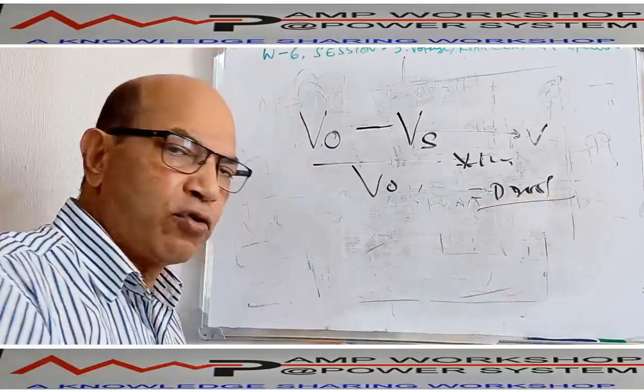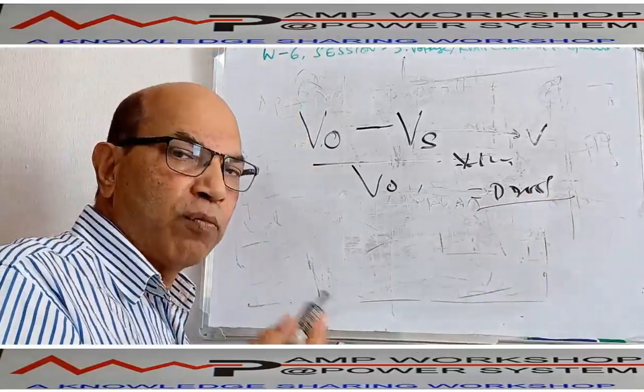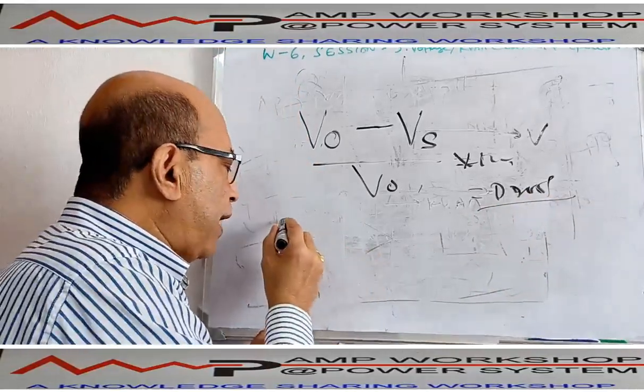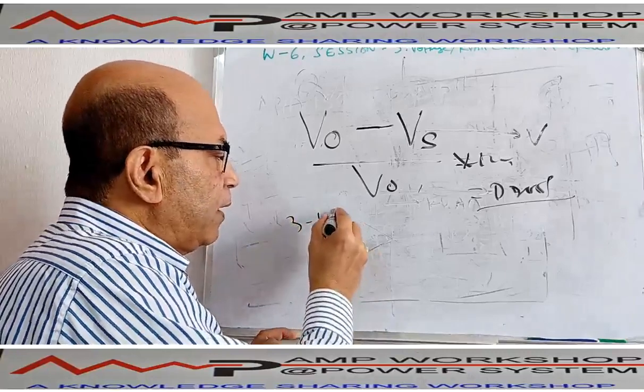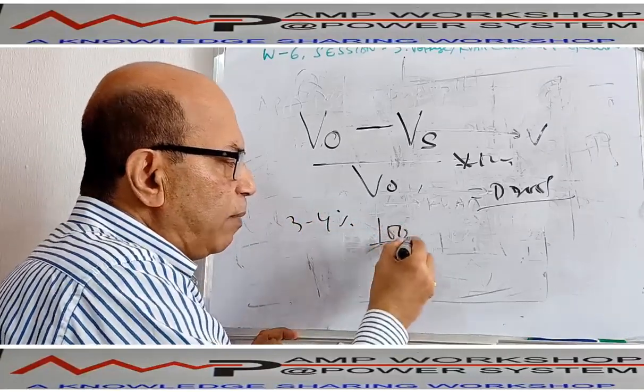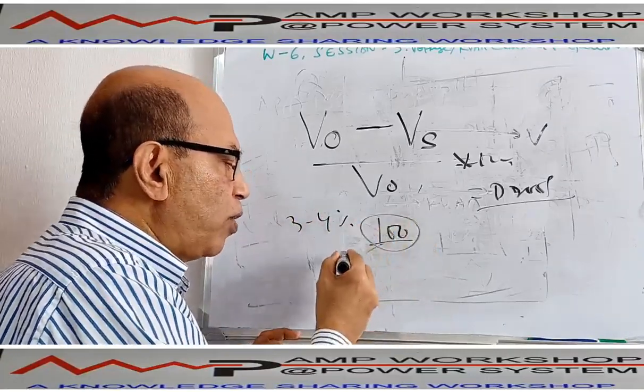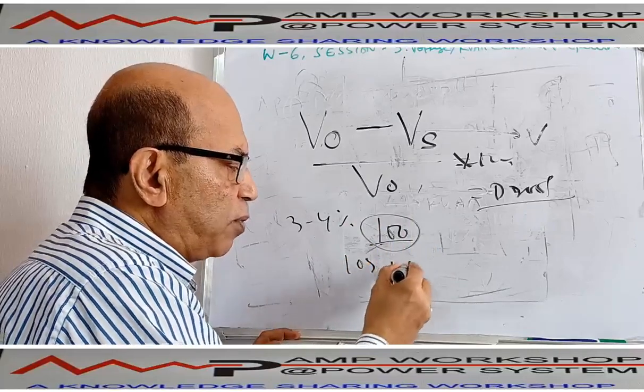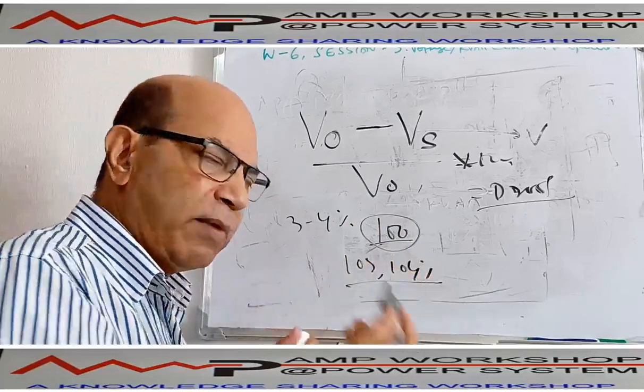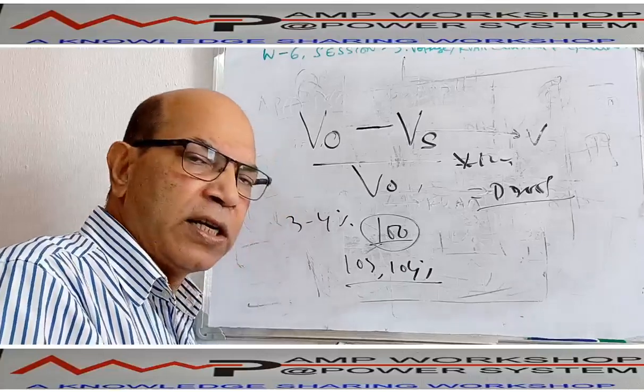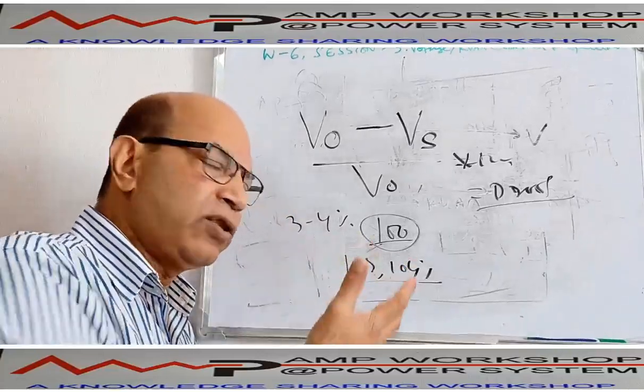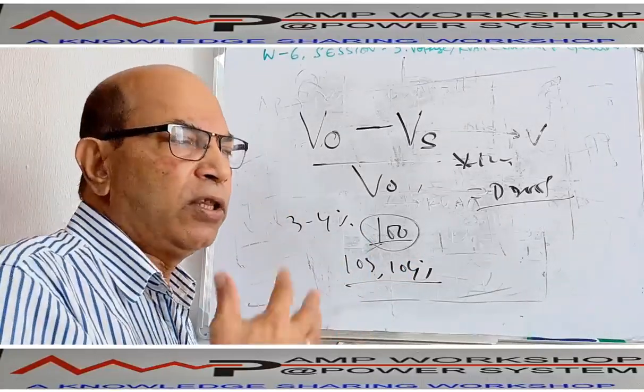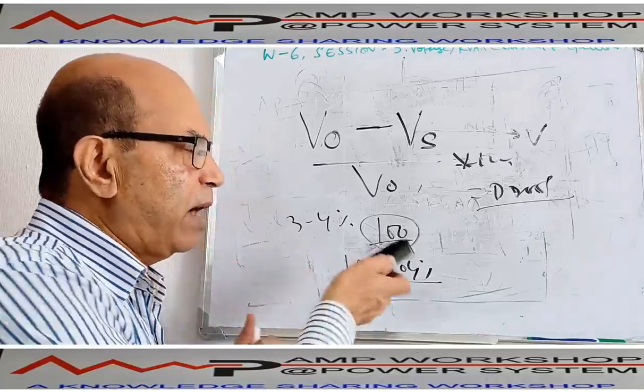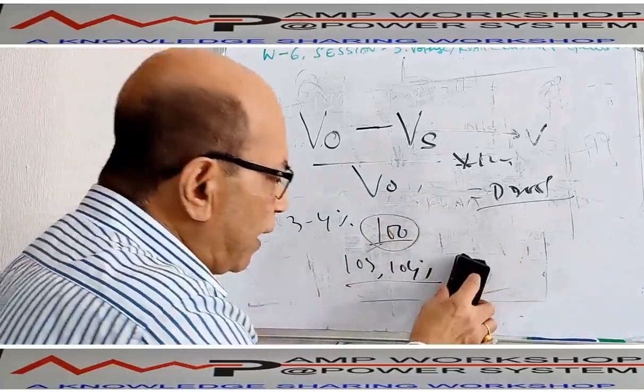Normally, when we want to run the generator in droop voltage mode, the droop setting varies between 3 to 4%. That means if 100% is the rated voltage, then you can put the droop at 103% or 104%. We do not increase it, same as with speed. As with speed, we do not increase more than 104%. Here also we generally maintain the droop within 3 to 4%, so maximum 104%. So this is the figure of the droop.